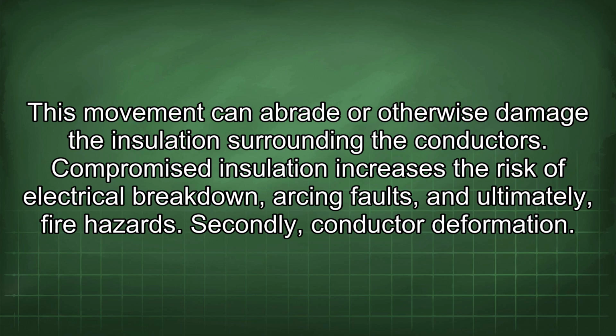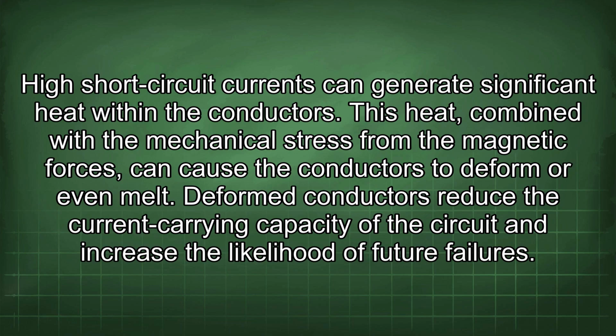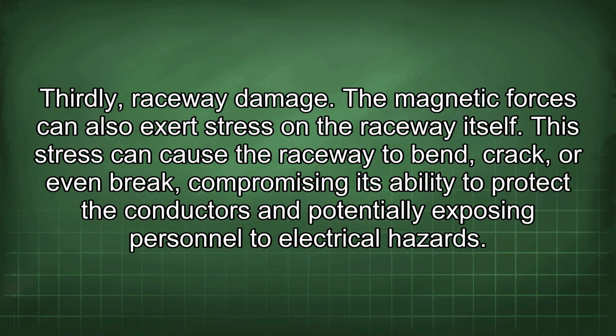Secondly, conductor deformation. High short-circuit currents can generate significant heat within the conductors. This heat, combined with the mechanical stress from the magnetic forces, can cause the conductors to deform or even melt. Deformed conductors reduce the current carrying capacity of the circuit and increase the likelihood of future failures. Thirdly, raceway damage. The magnetic forces can also exert stress on the raceway itself. This stress can cause the raceway to bend, crack, or even break, compromising its ability to protect the conductors and potentially exposing personnel to electrical hazards.